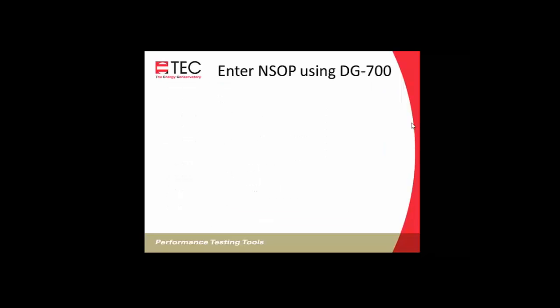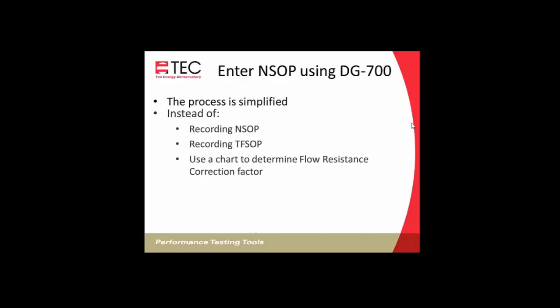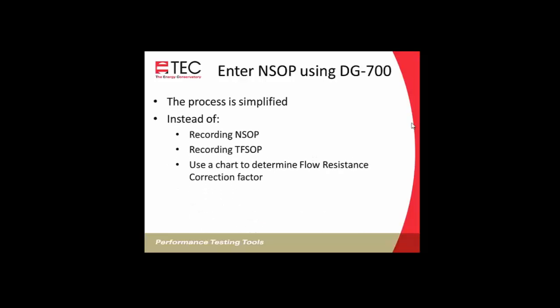Next, we'll enter the normal system operating pressure if we're using a DG700. And using a DG700 simplifies this process because instead of recording the normal system operating pressure and the true flow system operating pressure and using a chart or a formula to determine the flow resistance correction factor, it's all done internally.